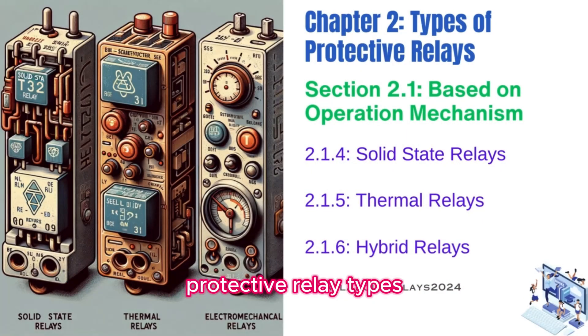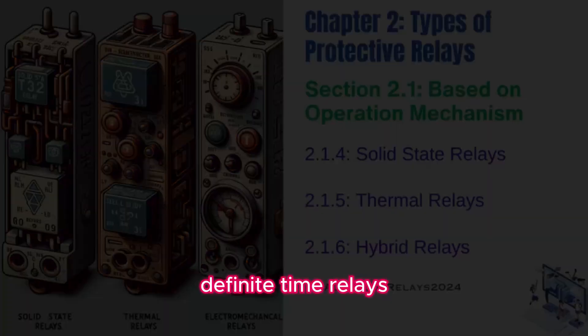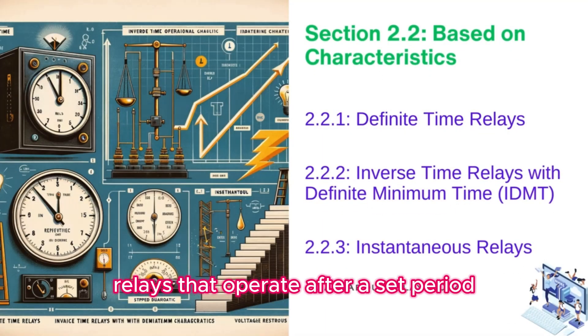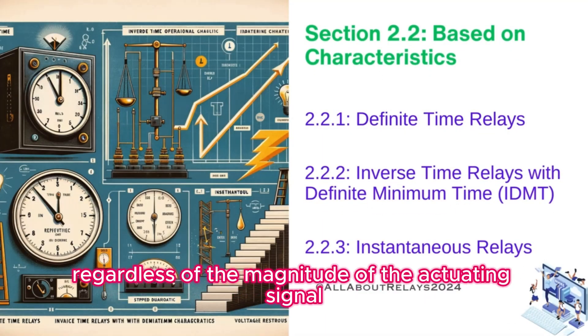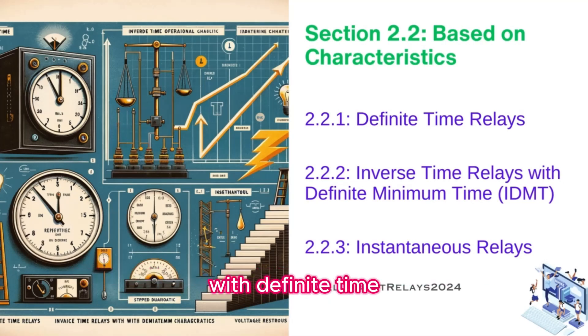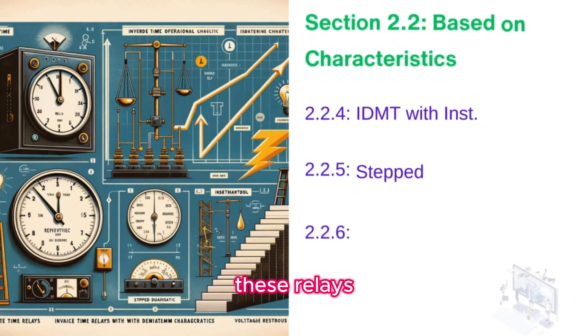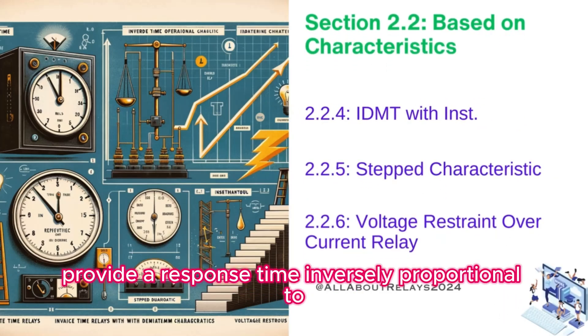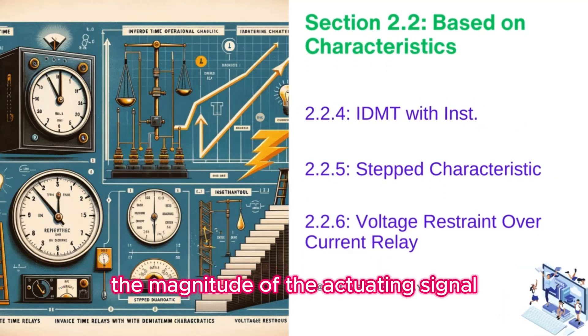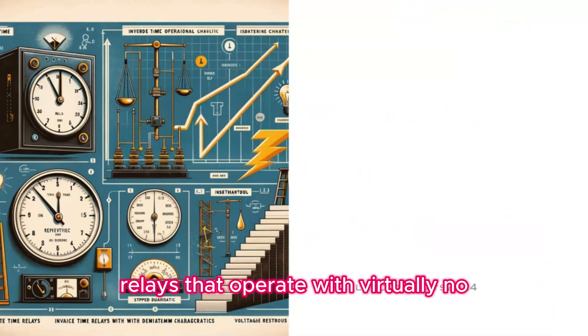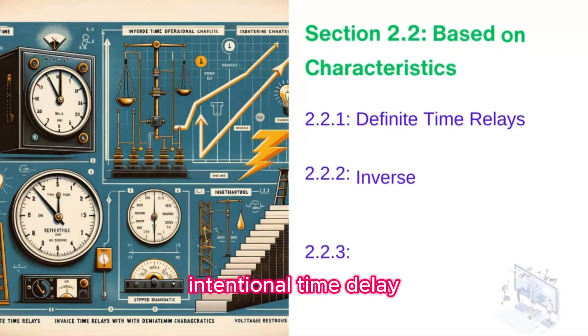Protective relay types based on characteristics. Definite time relays operate after a set period regardless of the magnitude of the actuating signal. Inverse time relays with definite minimum time (IDMT) provide a response time inversely proportional to the magnitude of the actuating signal. Instantaneous relays operate with virtually no intentional time delay.